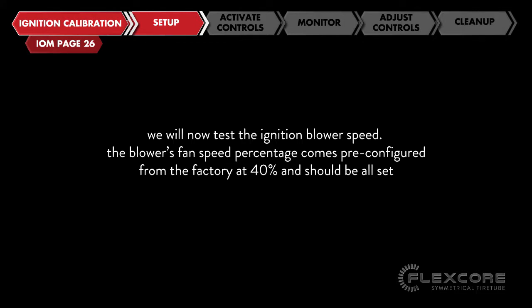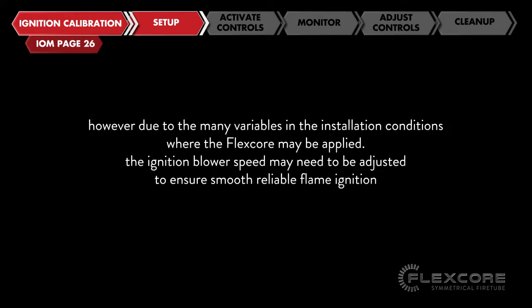We will now test the ignition blower speed. The blower's fan speed percentage comes pre-configured from the factory at 40% and should be all set. However, due to the many variables in the installation conditions where the Flexcore may be applied, the ignition blower speed may need to be adjusted to ensure smooth, reliable flame ignition.